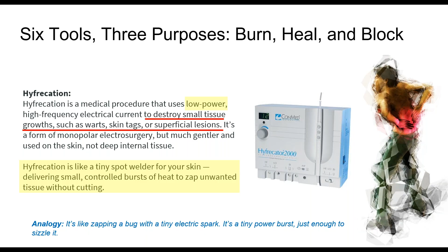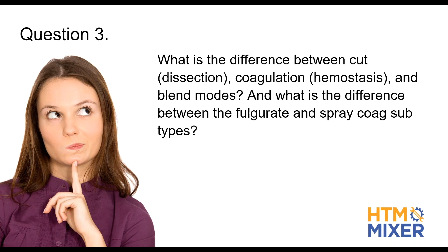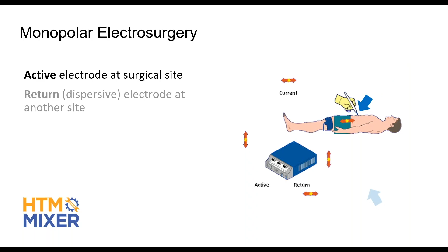What's the difference between cut or dissection, coagulation or hemostasis, and a blend of those two? Because I didn't know what audience I'm going to get. I don't know what background you have in electrosurgery, so I'm going to explain these real quickly. First of all, in monopolar electrosurgery, we have an active electrode, and we have a return electrode right here.